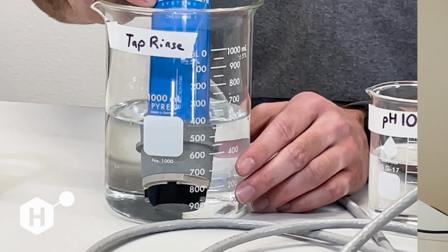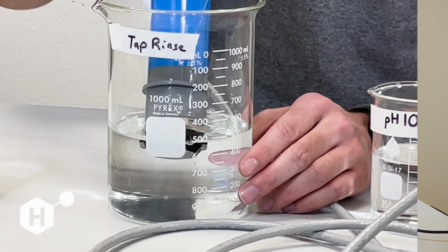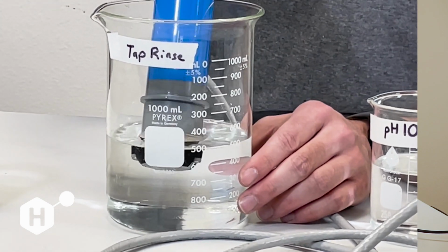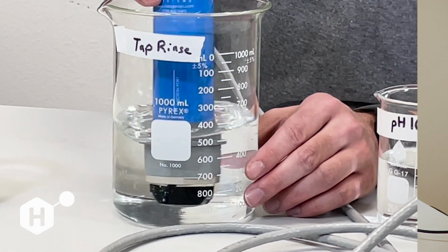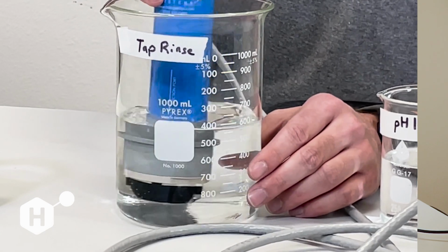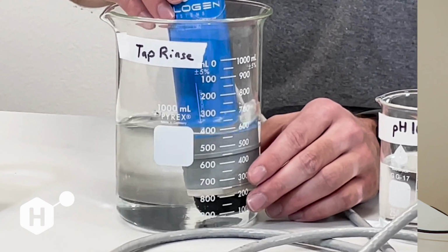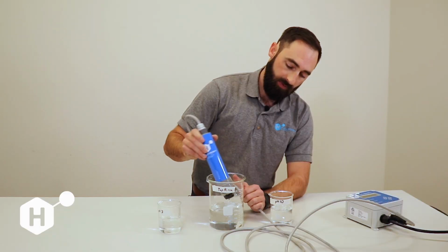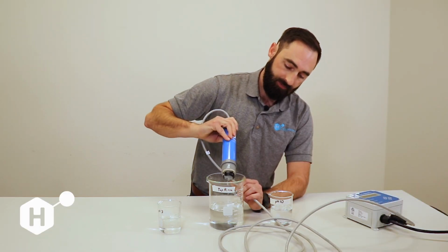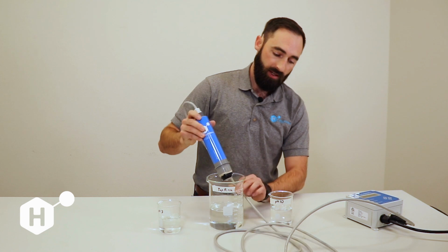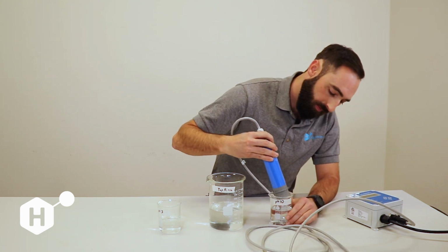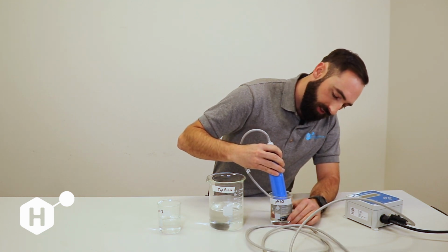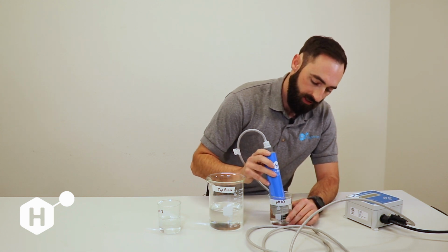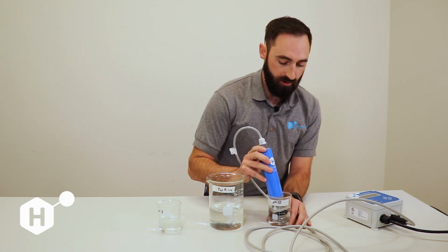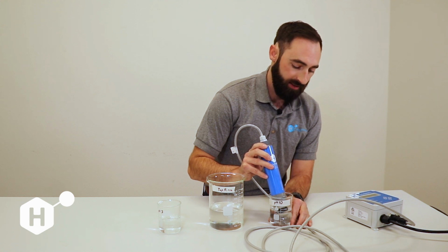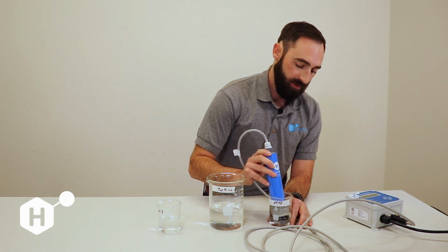And as you can hear now, the sensor sounds quite a bit different, and sure enough, we do have good flow across the sensor surface. We're just going to swirl it in here a little bit. Let us get as much of that 7 buffer out of there as we can. And then we're going to do the same thing. We're going to pull it up, get all of that water out of there, and then move it into our 10 buffer. And luckily this one primed right off the bat, but once again you're going to want to confirm with your ejection port that you're seeing water exit that ejection port, like so.